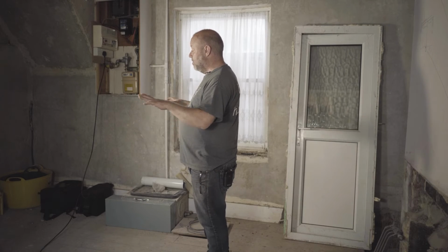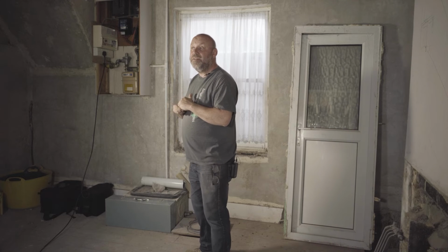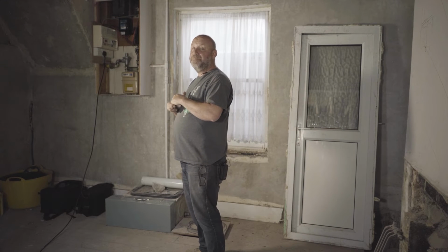Because that's a completely uninsulated space that's potentially got lots of drafts as well, we should really insulate this floor, but it's a discussion that needs to be had with the customer because there are some costs involved in doing it, and it wasn't ever part of the original programme of works because they originally were going to have radiators and then only later on decided they wanted to change this to underfloor heating.